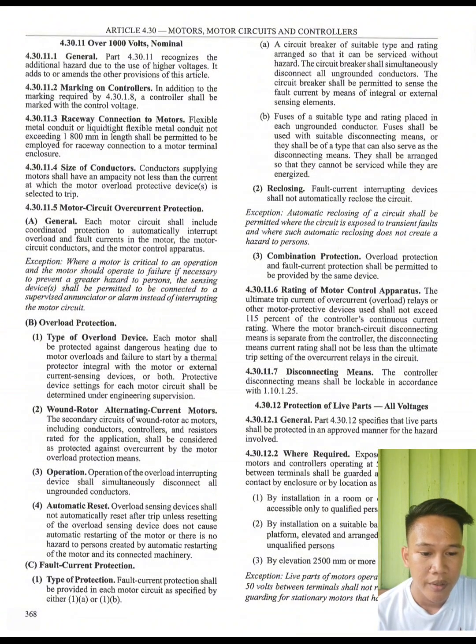2. Reclosing. Fault current interrupting devices shall not automatically reclose the circuit. So, may exemption po ito. One exemption is automatic reclosing of a circuit shall be permitted where the circuit is exposed to transient faults and where such automatic reclosing does not create a hazard to persons. 3. Combination protection. Overload protection and fault current protection shall be permitted to be provided by the same device.